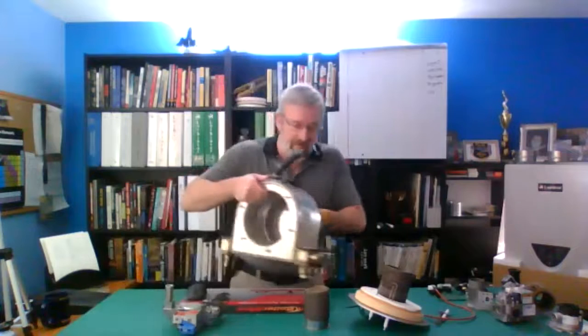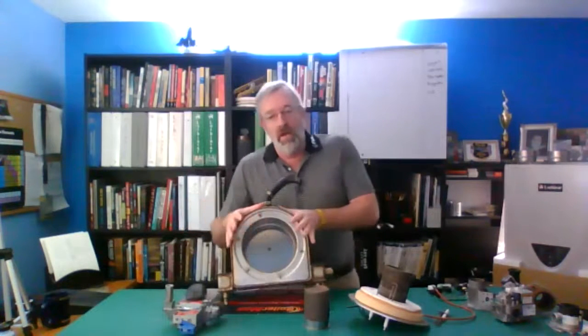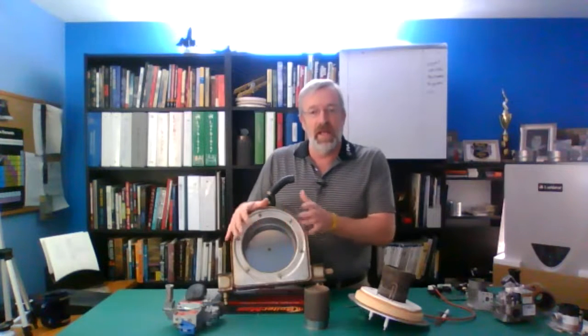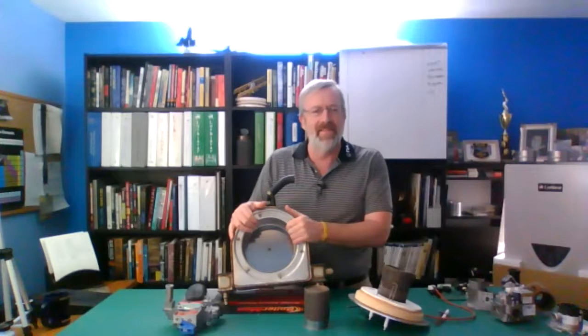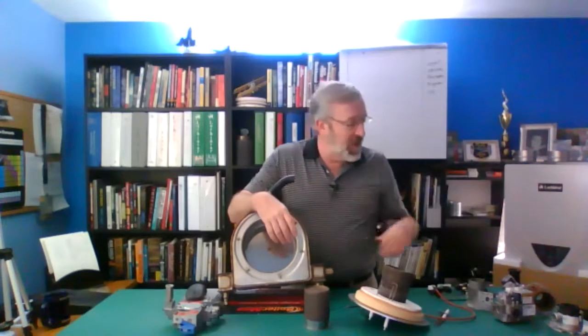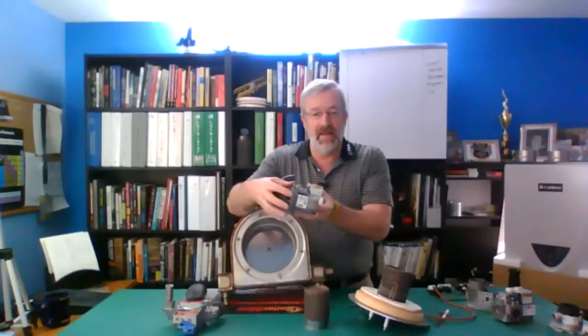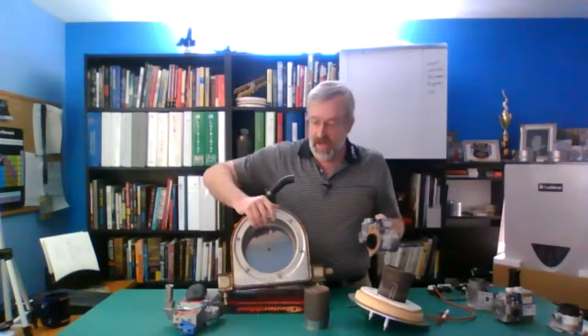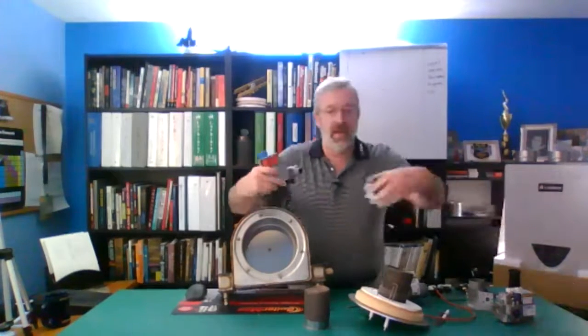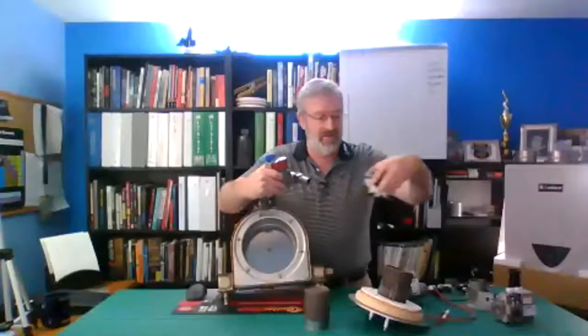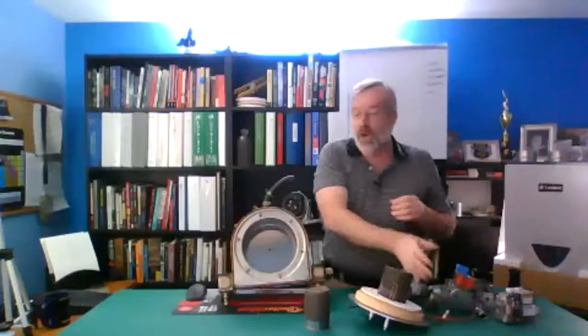So let's spin this guy around. All the burners really come out, I should say, come apart in the same fashion. Generally, the first thing that you're going to do is disconnect the gas valve from the fan. Now that works in two different ways. When I have the older 5-to-1 style, what I'm doing is I am disconnecting right here. I'm going to take this off the fan. As I get into the newer 10-to-1 style, right here I've got a G-nut on that, if you will, connected here. I take that off. Now at that point in time, my fan and my gas valve are disconnected.